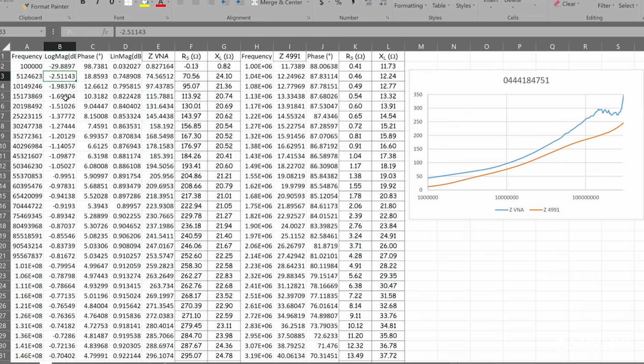The raw data that we got in here is in column B, so this is the log mag S21 readings that we saw on the screen. That was saved to a CSV, and then we imported it into Excel. So we had to convert that over to linear magnitude in column D here. And then since we're using a shunt through method, we had to multiply the linear magnitude over the reciprocal of the linear magnitude multiplied by 25 ohms to get our impedance of the part.